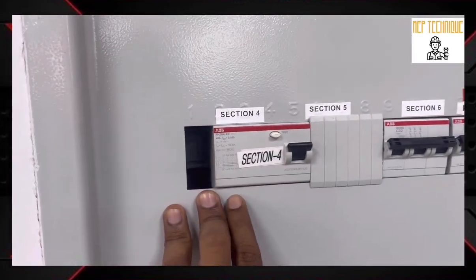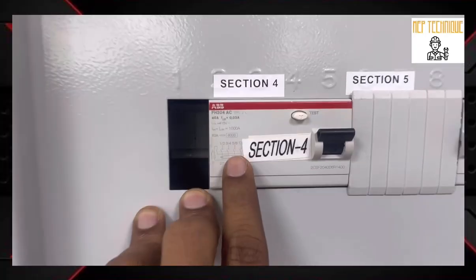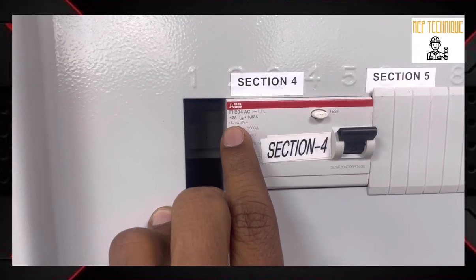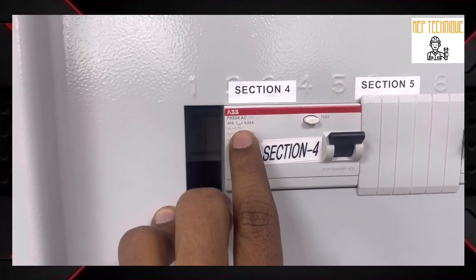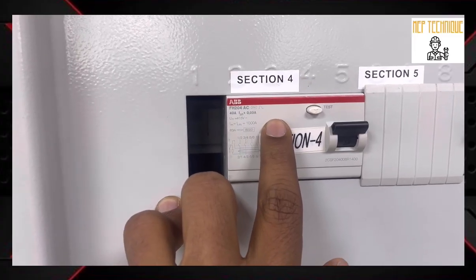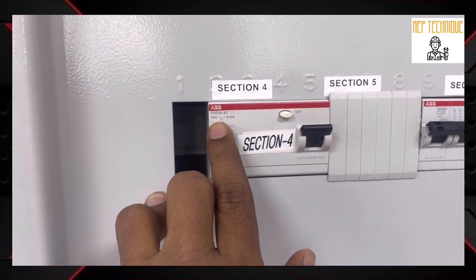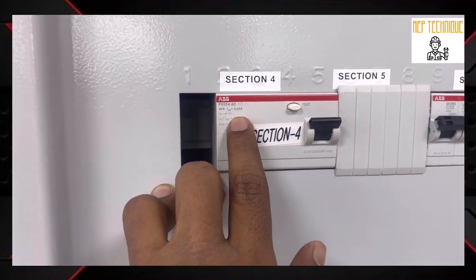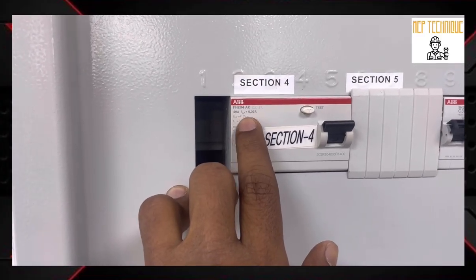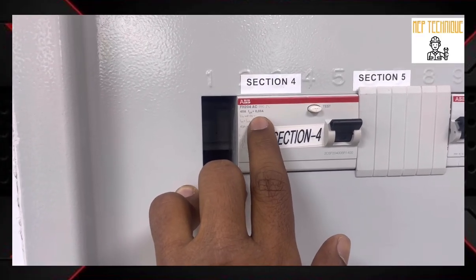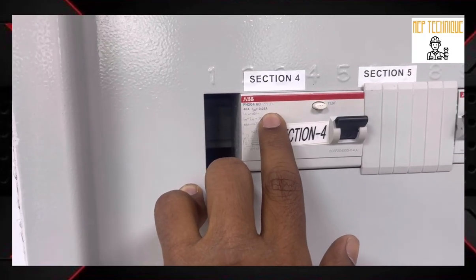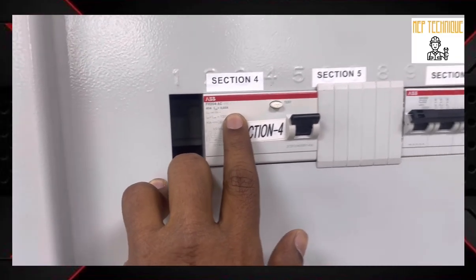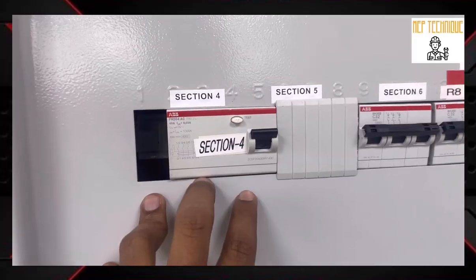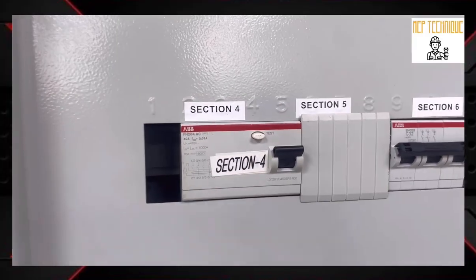So in front of us there is a 30 milliampere ELCB. This is 40 ampere, I delta N 0.03 ampere. That means the rating of the breaker is 40 ampere. I delta N means I is current, delta N means differential. 0.03 ampere is equal to 30 milliampere. That means if the leakage current exceeds 30 milliampere, then your breaker will get tripped.